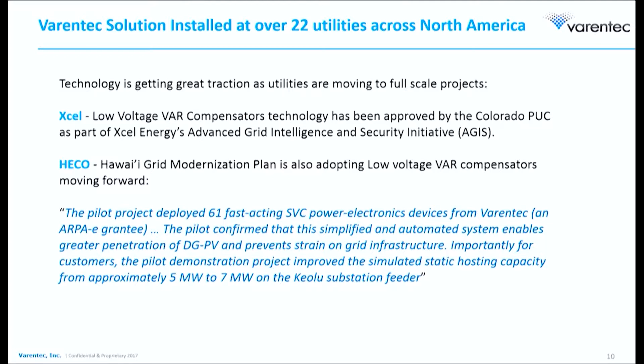In the case of HECO, I'll touch on it on a later slide. We had a very successful pilot with HECO, and I pulled that quote from their grid modernization plan that just came out a couple of weeks ago. It actually singles out Varentec, talking about deploying 61 units on the feeder and how it stabilizes and improves reliability, and also allows hosted capacity to go from 5 megawatts to 7 megawatts on that specific feeder. So on top of improving reliability and power quality, you're also creating new space to include more DER and PV.